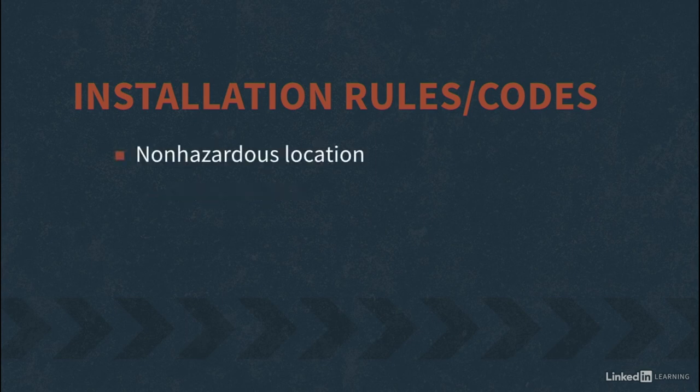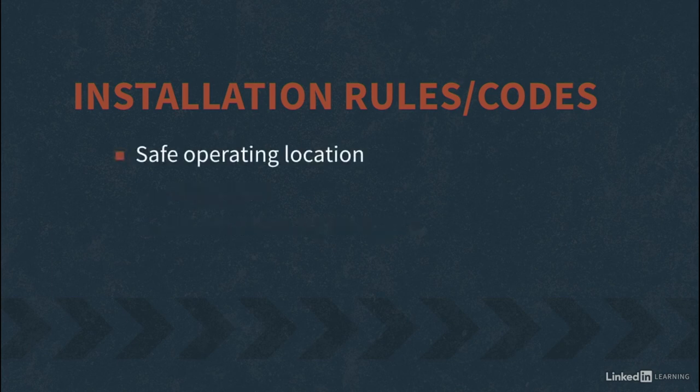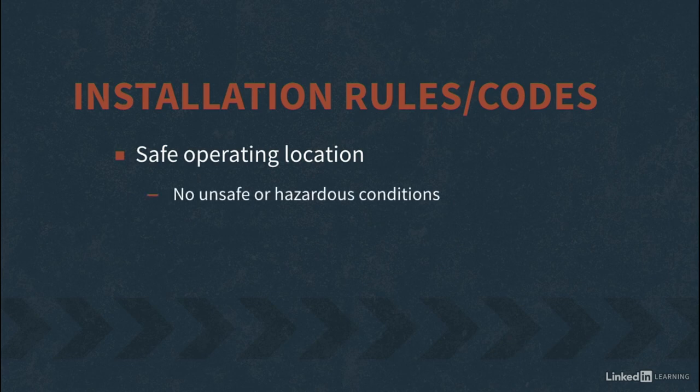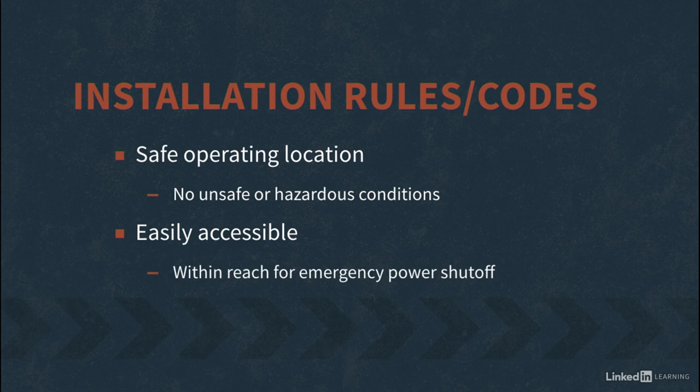Not installed in a hazardous location, such as wet or damp location, or an area that has other hazards like corrosives and explosive gases that can damage the equipment. In an area that lends itself to safe operation. Areas where the operator is not exposed to unsafe conditions or hazards, such as moving equipment or falling hazards. Easily accessible. It should be easily within reach so that the operator can shut off power quickly if they need to.